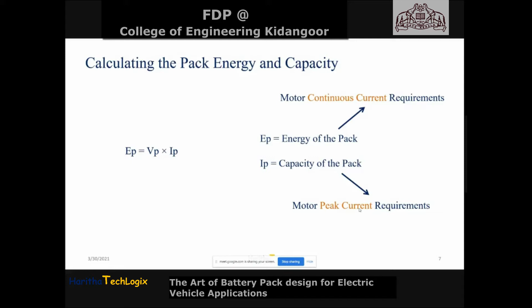So if I say 200 ampere is the peak current requirement, how long does it need that peak current - whether for 1 second, 2 seconds, 5 seconds, 10 seconds. The timing for which the peak current requirement exists is also very important to properly size the capacity of a battery pack cell. That is very, very important.